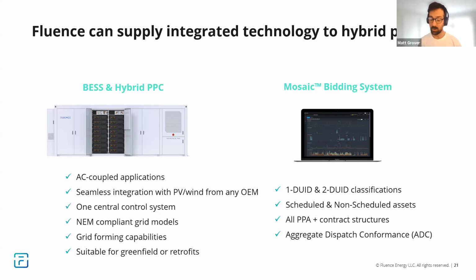For a wind farm, I imagine it's an altogether different consideration, because the nature of that generation profile would dictate quite a different battery sizing approach. Certainly if you have a one-DUID configuration of your hybrid plant, where your battery is required to buffer out the unders and overs, that would be a key consideration in deciding what size and duration battery to put in. The one-DUID wind farm gives me nightmares just thinking about how much energy that battery would have to reserve to always be there to back up the wind farm. So I hope that answers the question.